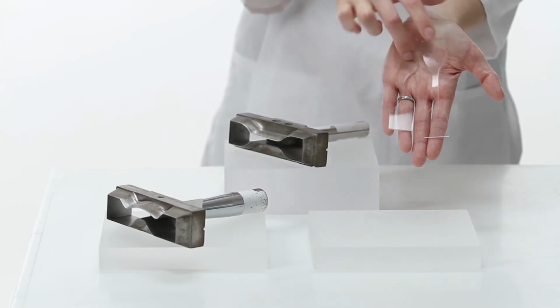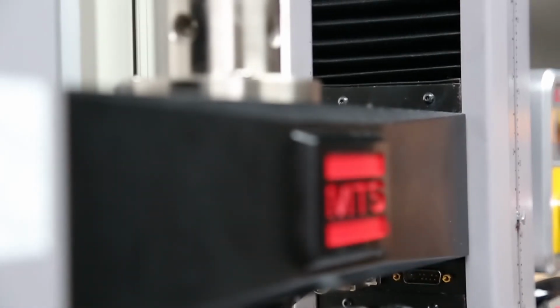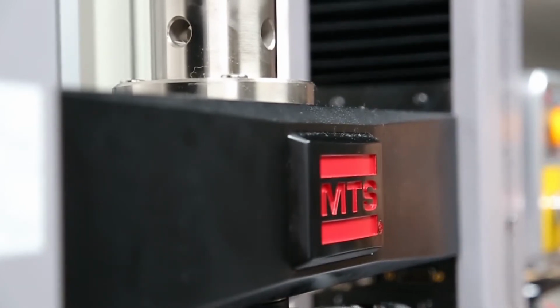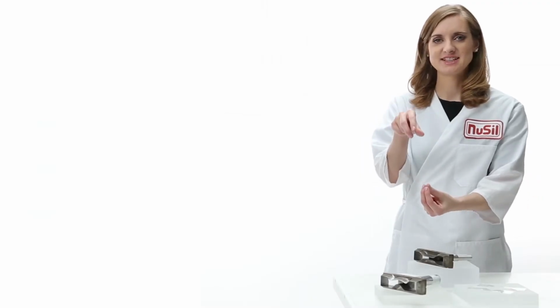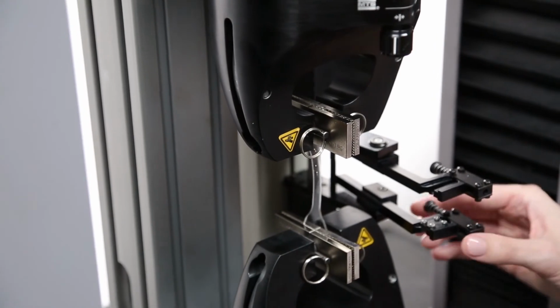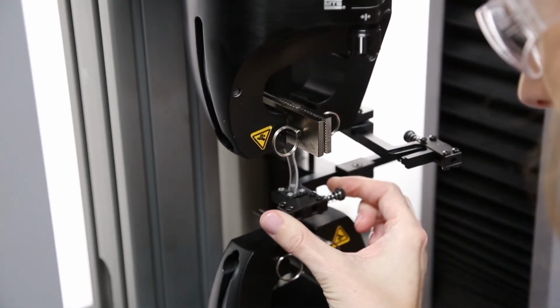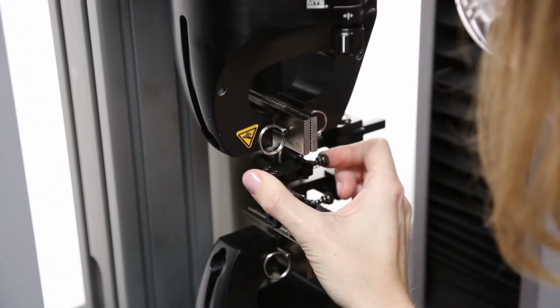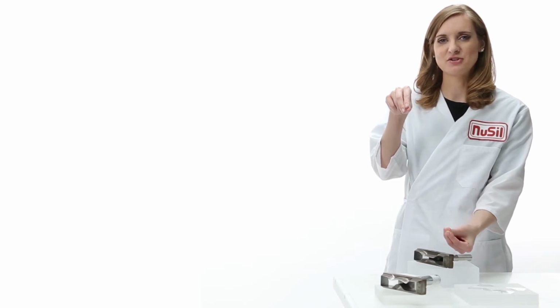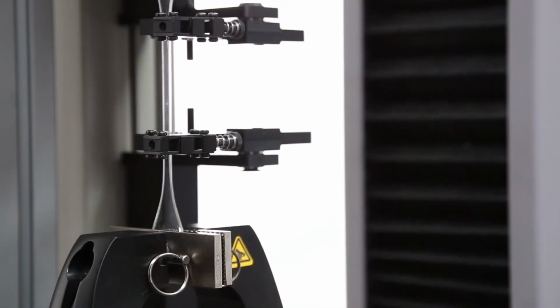The two bars are tested in the same way, but the tear bar will give you information about how a sample will react when a material is defected. We test tensile, elongation, and tear using an MTS. The sample is placed into the clamps, and the instrument pulls the sample until the material breaks.